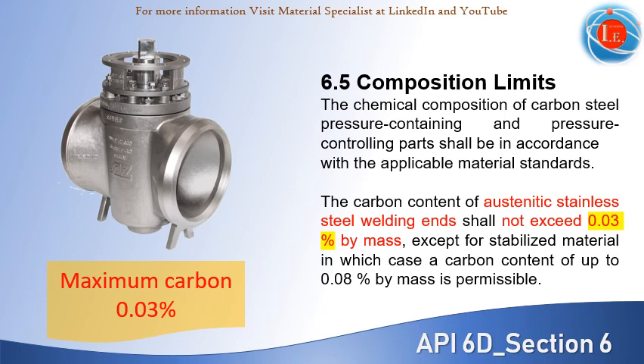One of the most important restrictions concerns austenitic stainless steel welding end valves, in which the carbon content shall not exceed 0.03% by mass. Apparently, this is an effort to avoid intergranular corrosion formation after welding and during operation.